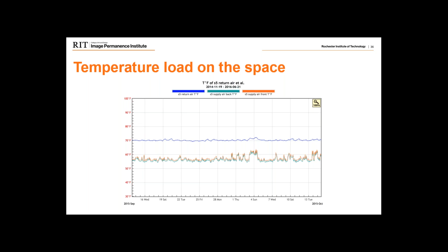And I mentioned earlier, knowing your envelope, knowing how tightly sealed it is. That room itself had gaps from old pipes, old ductworks in the surrounding spaces. Those surrounding rooms were being conditioned to about 70, 72 degrees. And those were playing a major factor. That cool air got brought up in the ceiling. It was mixing with air from halls, from the room above, from wherever, that was raising that temperature. So that cool air coming out of the room, that condition was lost and brought back to the unit warm. And that mechanical system then had to reduce this temperature again using more energy. And it's something that the staff and the maintenance didn't really understand or know what was going on for that space.